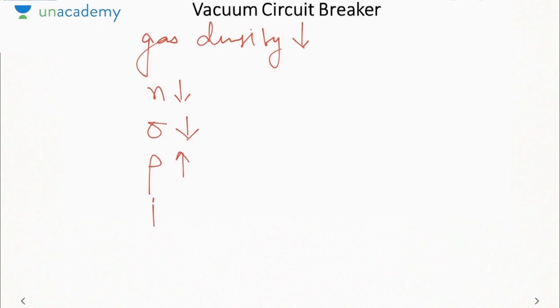The last is your vacuum circuit breaker. Here we eliminate the medium between the contacts of the circuit breaker, because if there is no medium between the contacts, then there will be no ionization and no charge carriers produced. But it is very difficult to obtain a perfect vacuum. So what we are essentially doing is reducing the gas density. If gas density is very low, then the number of charge carriers will be reduced, due to which conductivity reduces, resistivity increases, and arc resistance also increases. If arc resistance is high, then the current flowing will be very small and it is easier to extinguish the arc. So that is your vacuum circuit breaker. It is the most efficient circuit breaker. So here what we have done is eliminated the medium between the circuit breaker plates.